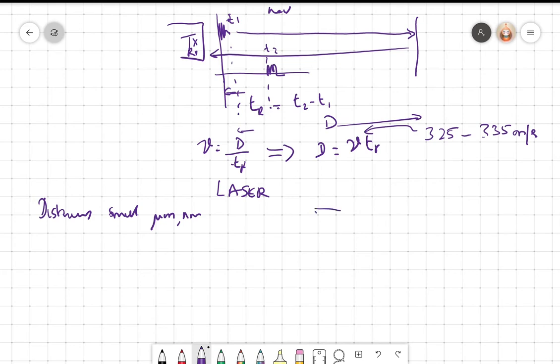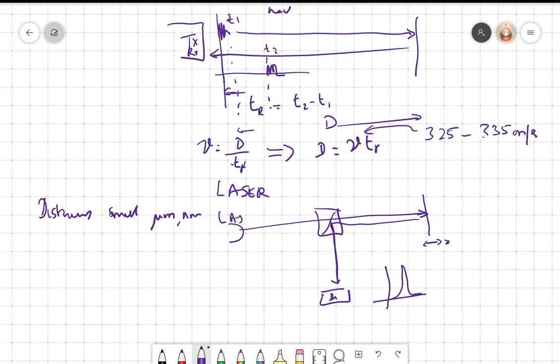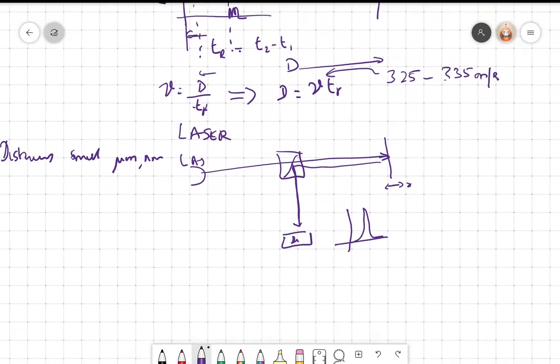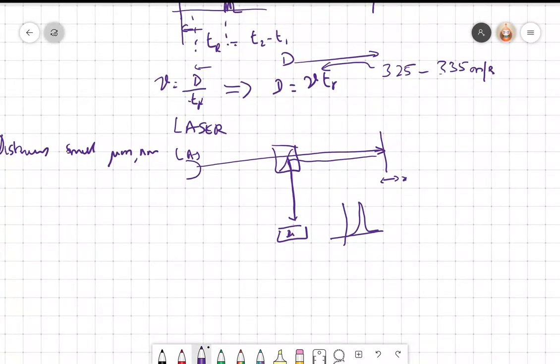So, for example, if this is moving by x, say micrometers or nanometers, then we send a laser, a coherent beam, and the laser comes back, and if you put a detector here, we get an interference pattern, and by measuring the amount of interference, we can measure displacements which are in terms of a fraction of the wavelength of the laser. For example, if I use a helium neon laser, which is approximately 600 nanometers, I can measure distances in terms of nanometers very accurately. So this is also a method.